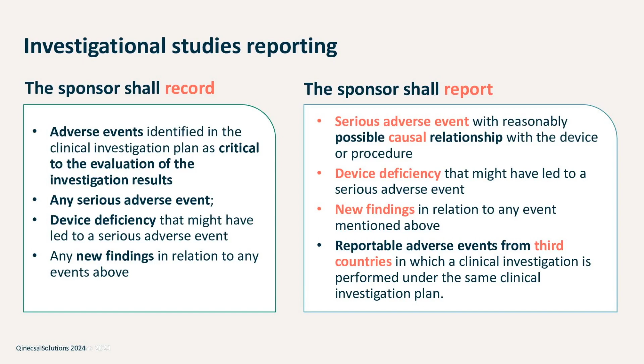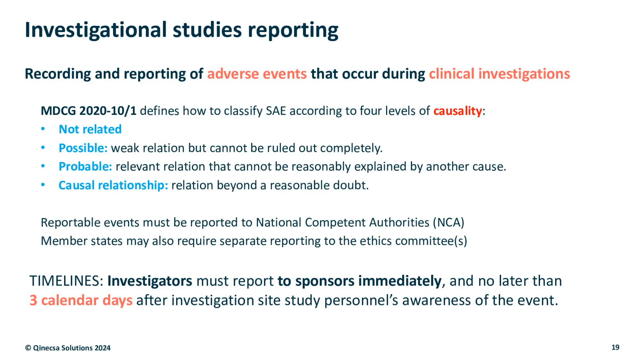In investigational studies, there's an MDCG guideline 2020-10/1, and that classifies serious adverse events into 4 levels by causal relationship. That is different from drugs, so it's important to have the database properly set up to make sure that the correct scale is used for devices.